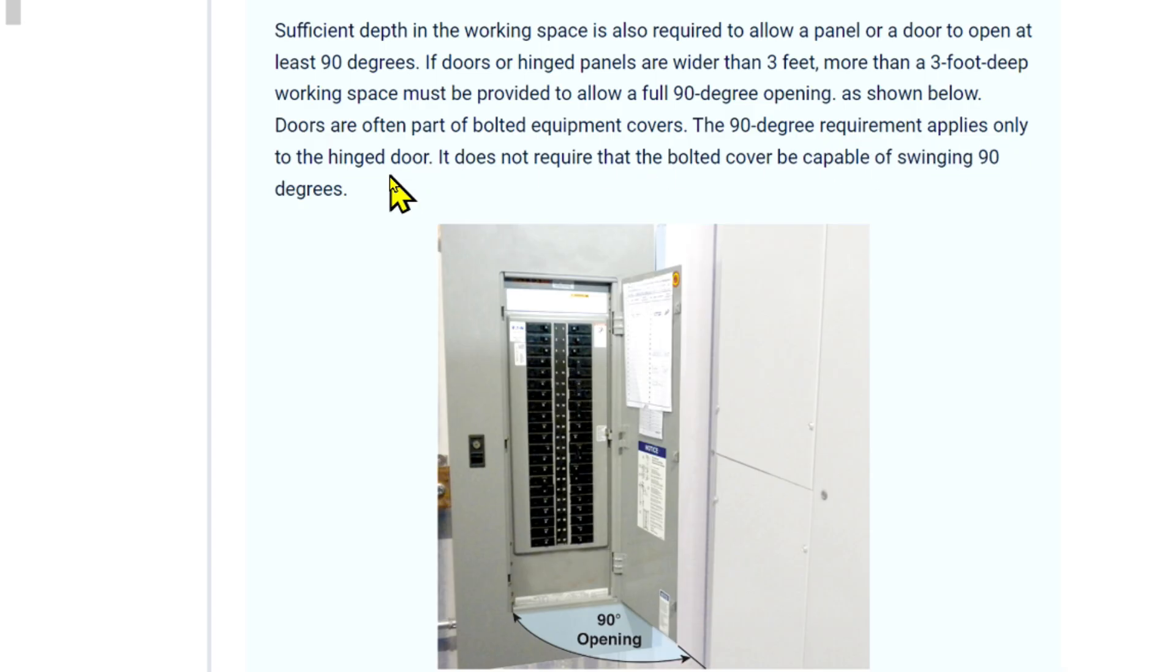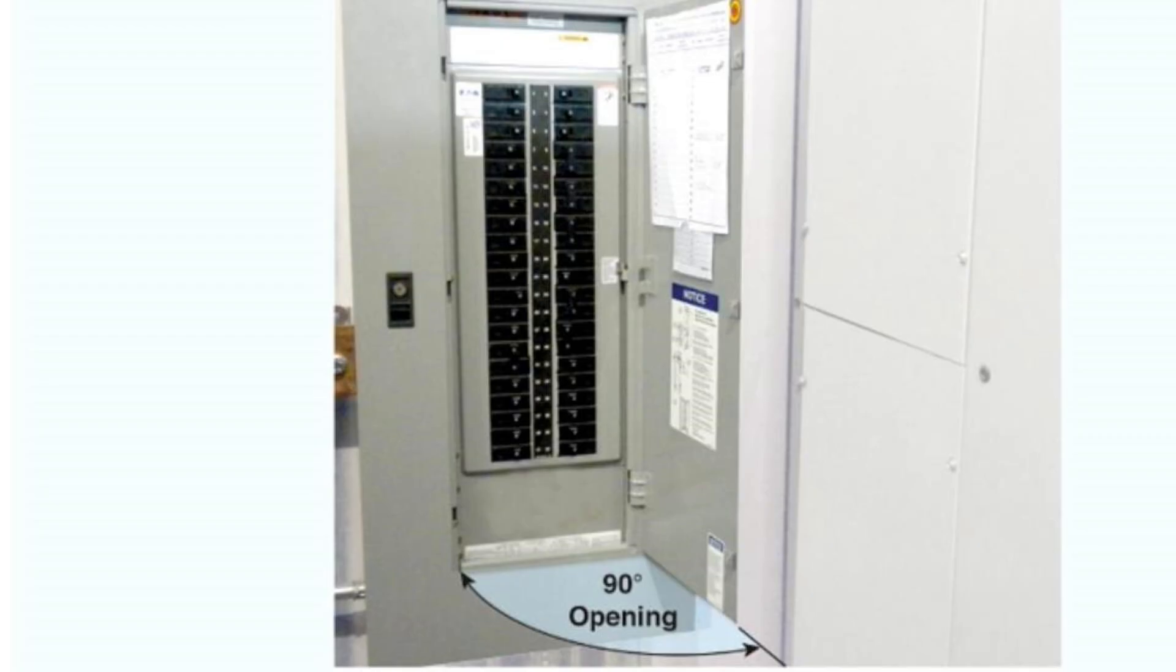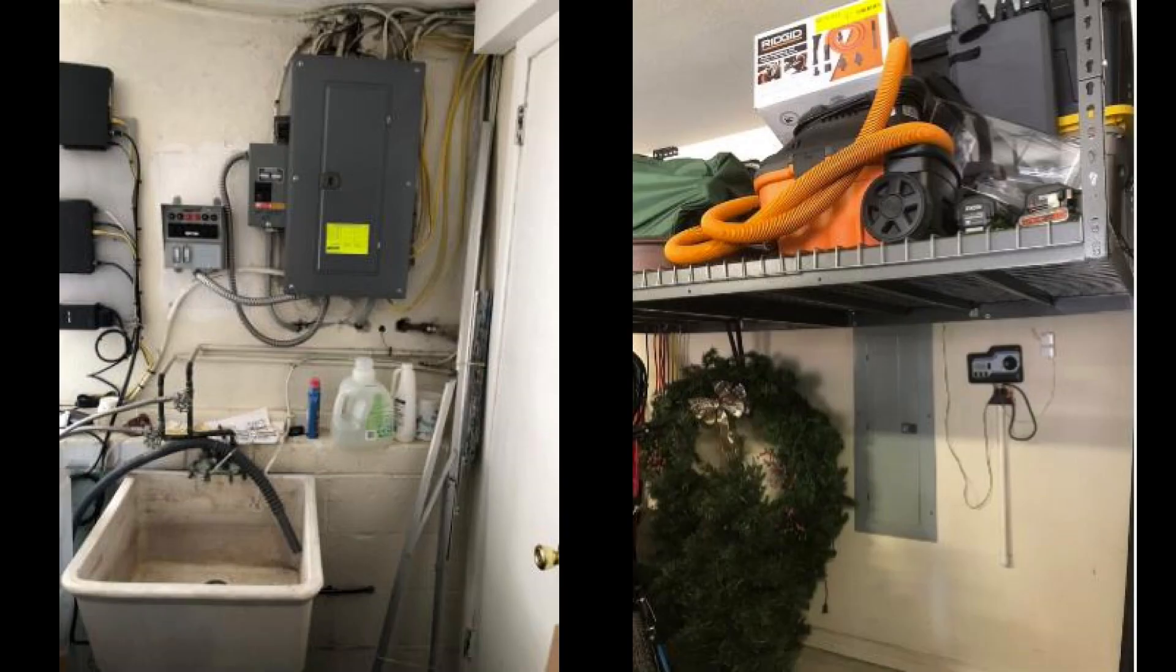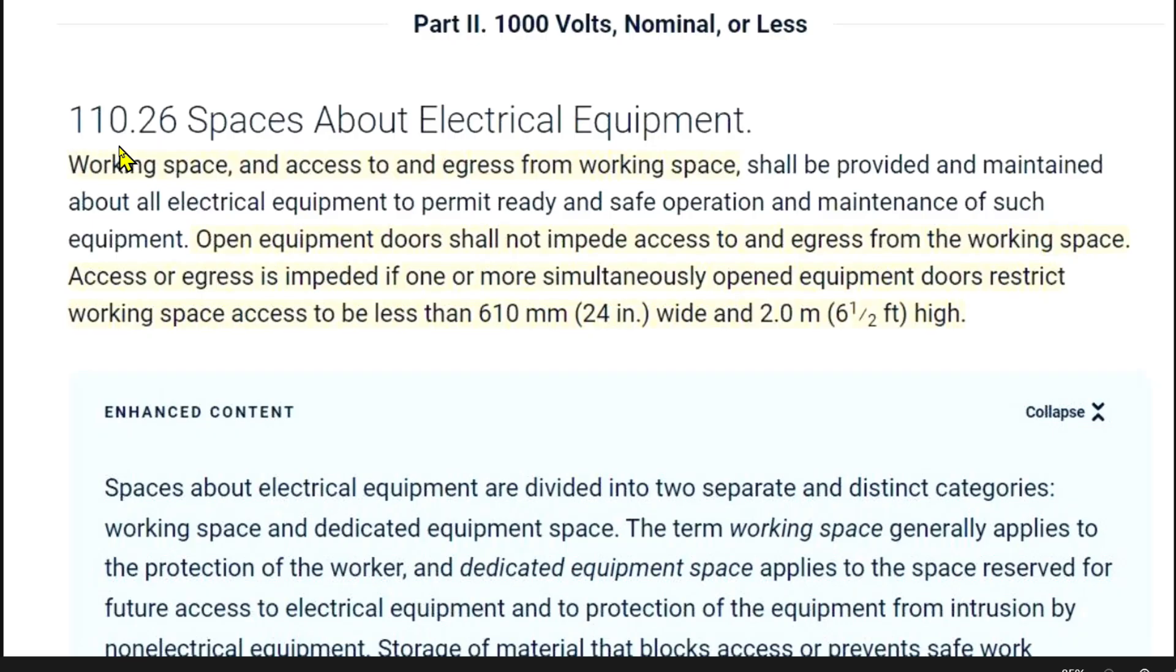Doors are often part of bolted equipment covers. The 90 degree requirement applies only to the hinged door, it does not require the bolted cover to be capable of swinging 90 degrees. Notice that in this case the bolted equipment cover goes all the way to the floor. There is no prohibition against this.